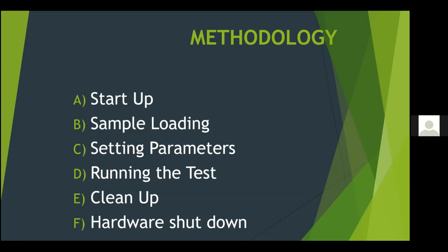So the second step is the option that ensures cleaning of cells with detergent before every sample scan was selected, which should be followed by multiple water rinse steps to ensure no detergent residue was left in the cells. And then the starting temperature of the experiment was set to 20 degrees Celsius, the final temperature to 100 degrees Celsius, and then the scan rate to 60 degrees Celsius per hour, which was the common scan rate.